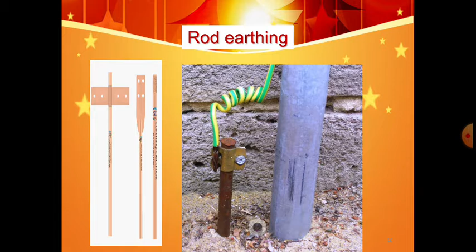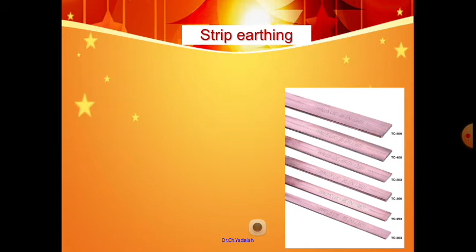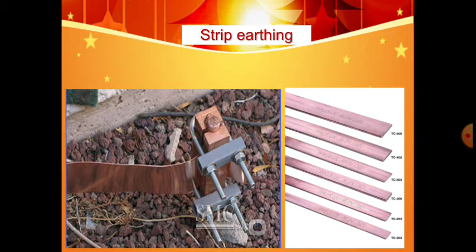Another type of earthing is strip earthing. Here copper strips are used as earth rods. The copper strips are placed here, and this is used for the earth pit. You can see here an example of strip earthing. Another type is plate earthing. Here is a copper plate, 60 centimeters by 60 centimeters and 3 mm thick. The copper plate is generally used where it is not possible to go to depth.